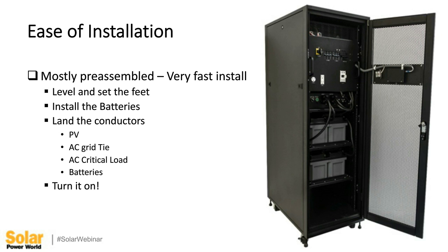You're looking for the same kind of thing with a hybrid system: something mostly pre-assembled, with a very fast install. You don't want to be out there wiring all the little control wires, communication wires, and power wires. If it's floor mounted, you want to be able to roll it in, level it, install the batteries, land the conductors—your PV, your AC grid tie, your critical load AC support, and the batteries should all be there.